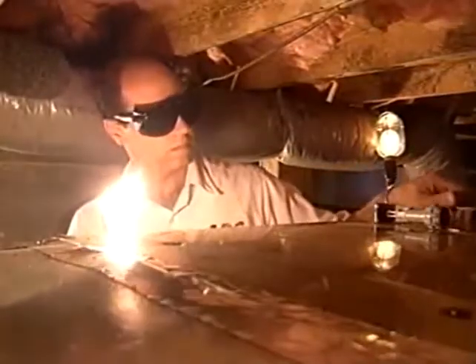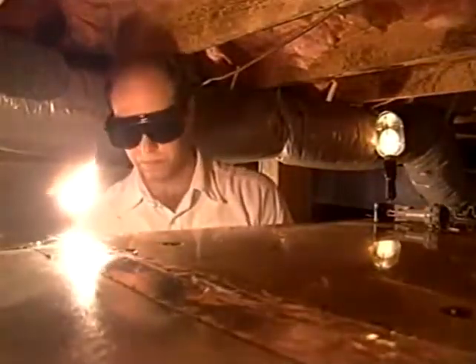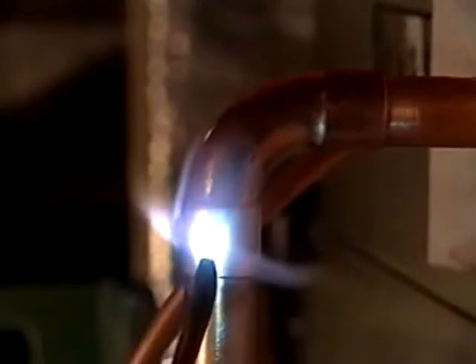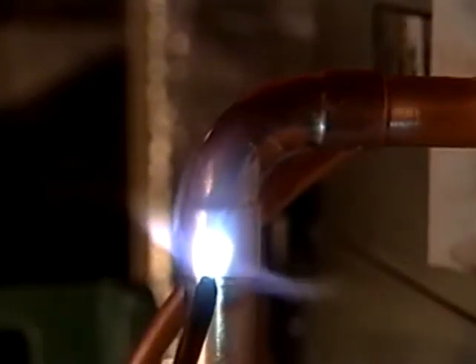Before brazing, clean the end of the pipe with an abrasive cloth. Check your tanks to make sure you have the correct amount of pressure. Nitrogen is recommended to minimize carbon buildup inside the solder joints. If your flame is not hot enough, you will not be able to braze the line properly. If it flows well, generally speaking, that's an indication that the rod is flowing smoothly. If it's going on kind of bumpy and rough, well then you may want to check your temperature and make sure you've got the right amount of heat on the joint.